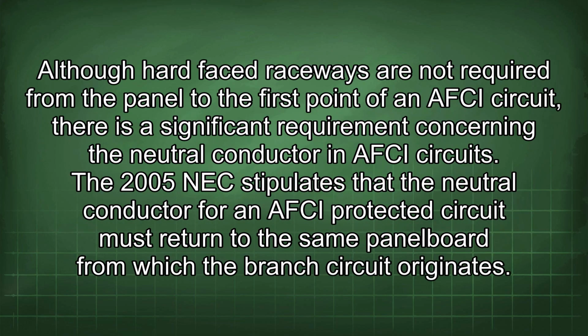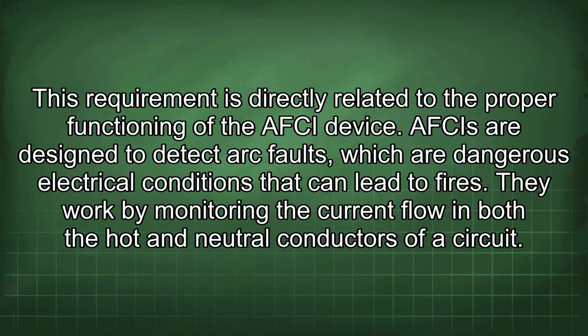jurisdiction. Although hard-faced raceways are not required from the panel to the first point of an AFCI circuit, there is a significant requirement concerning the neutral conductor in AFCI circuits. The 2005 NEC stipulates that the neutral conductor for an AFCI-protected circuit must return to the same panel board from which the branch circuit originates. This requirement is directly related to the proper functioning of the AFCI device.